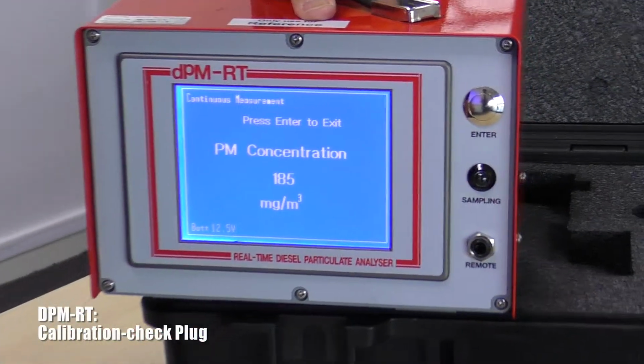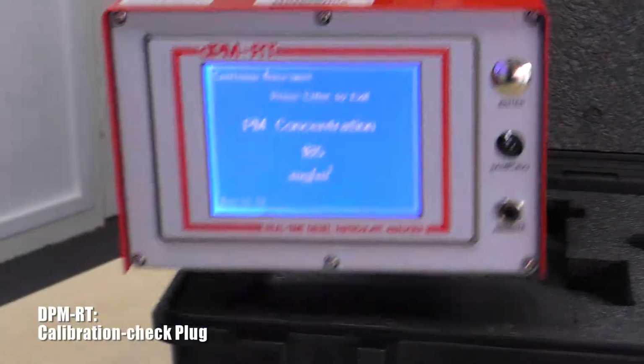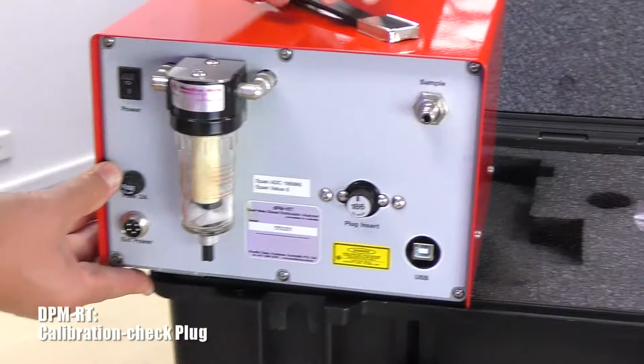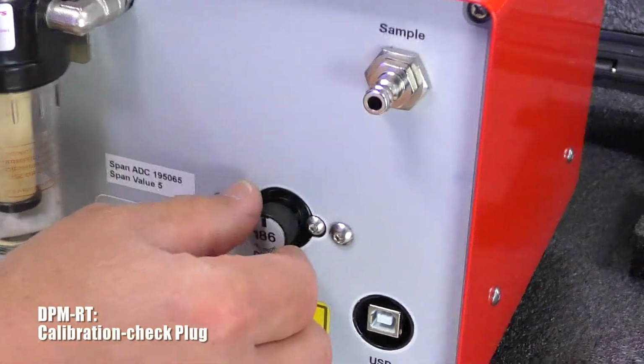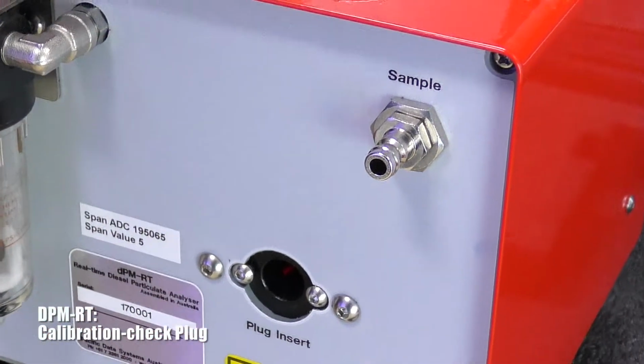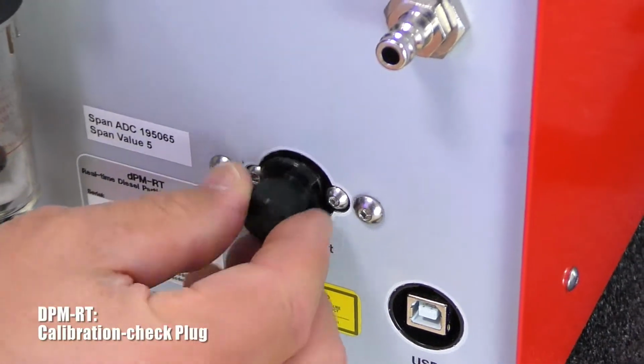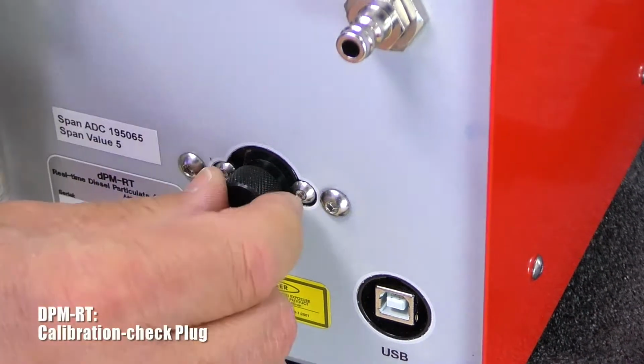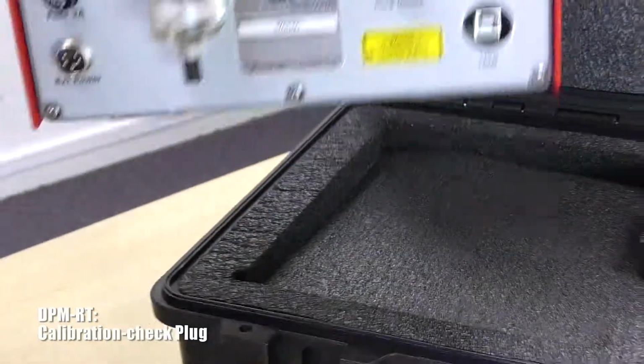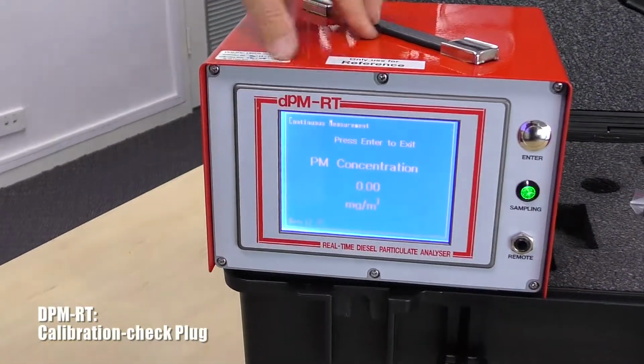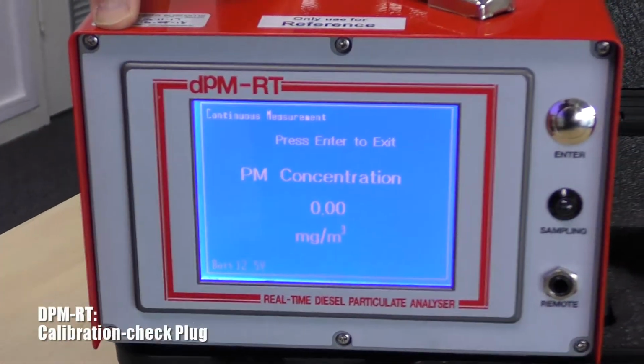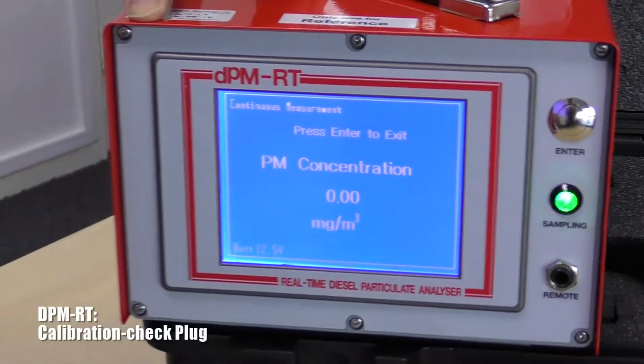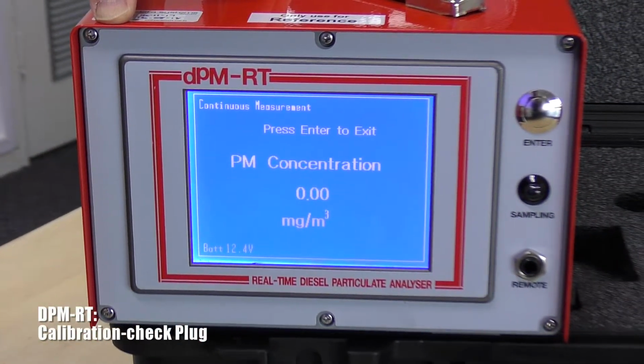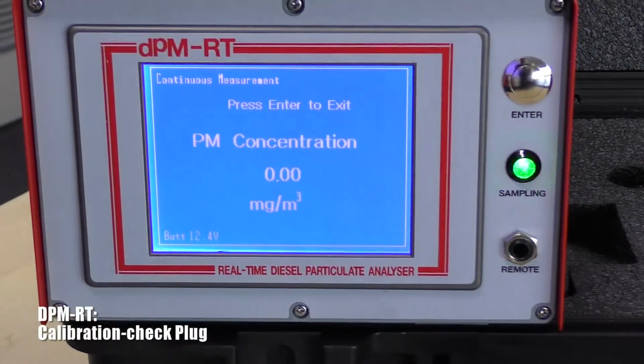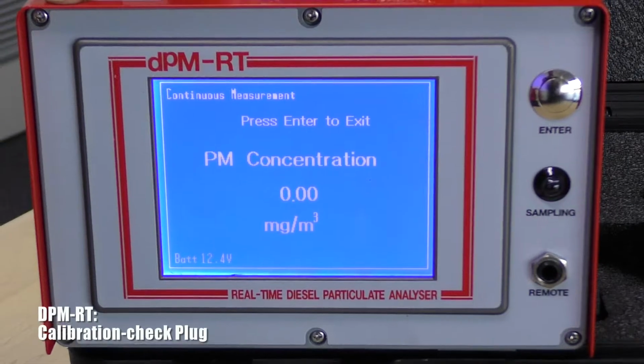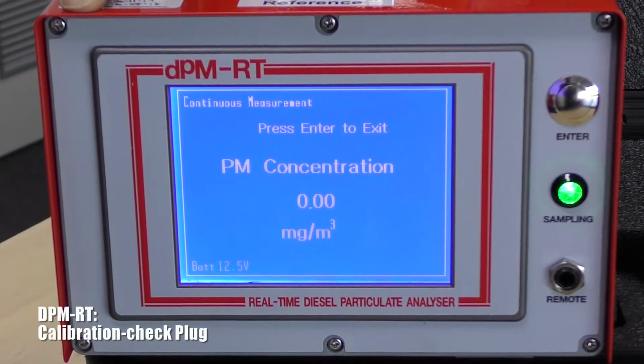For demonstration purposes, I'll replace the standard plug insert to demonstrate that the instrument will return to zero. Remove the calibration check plug, insert the plug insert, and as the instrument conducts a number of readings and then averaging and then displays, you'll notice that the number on the screen was falling as I rotated the instrument around, and now it's displaying 0.00 milligrams per cubic metre.